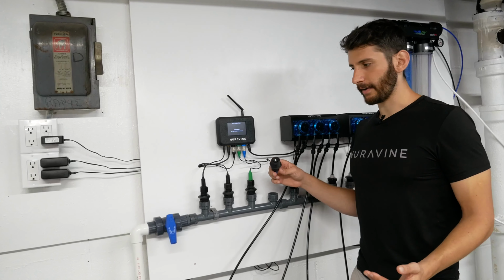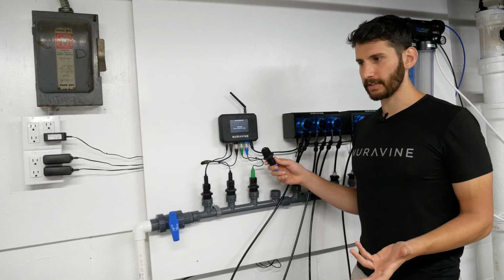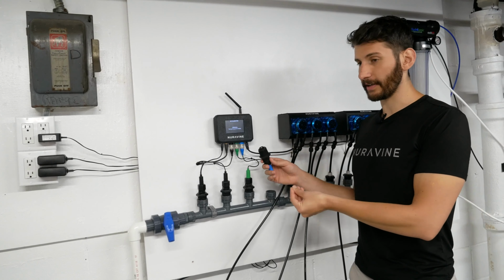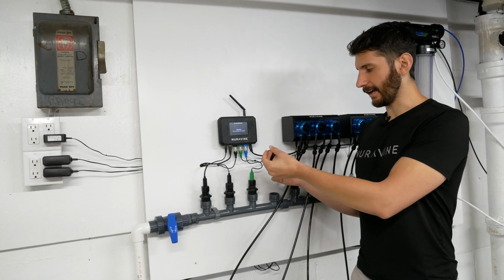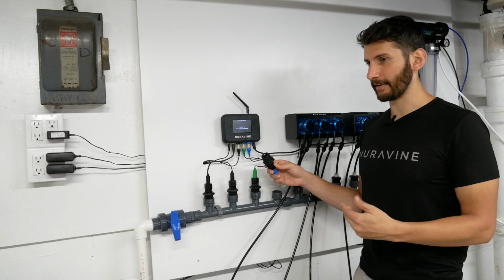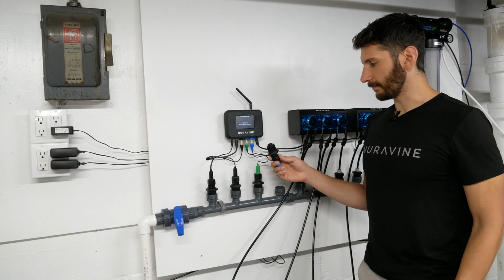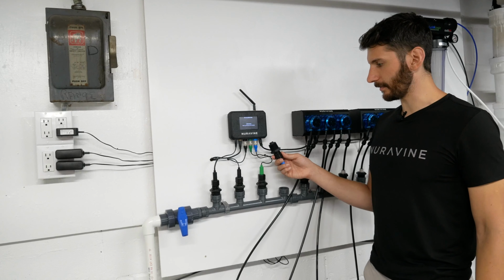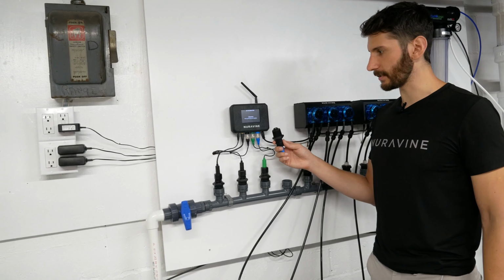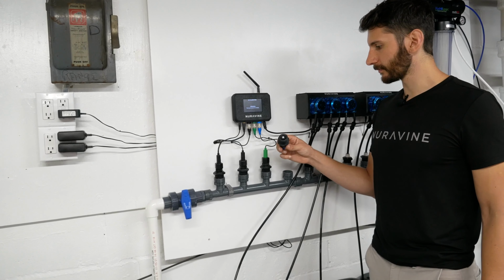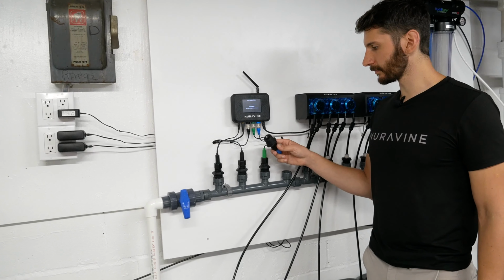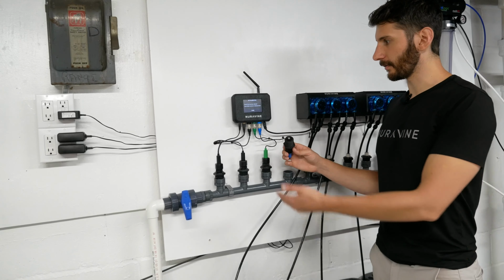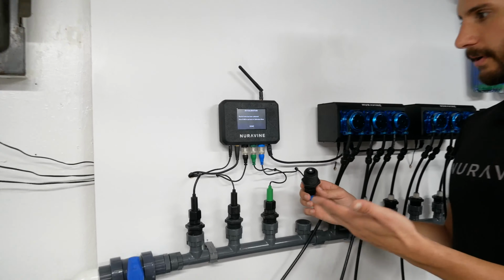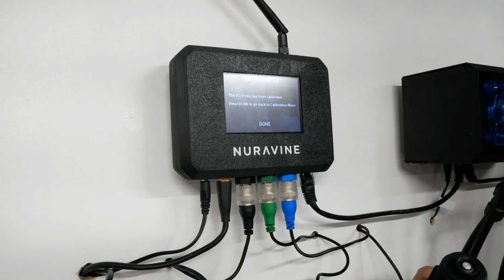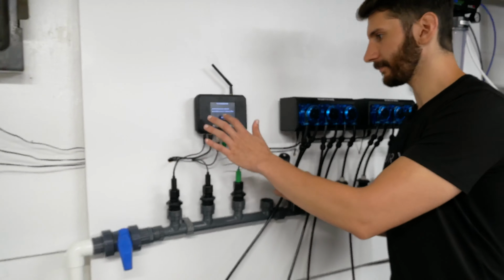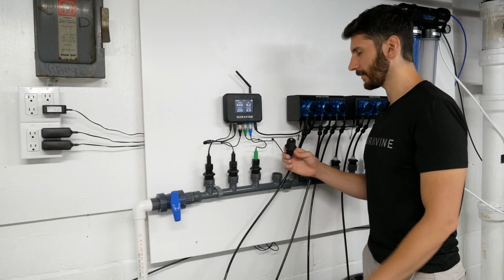Now the reason that I move it around is because this actually consumes oxygen. So theoretically, if you leave it in the very same spot, oxygen could be taken away from that spot, and then eventually the oxygen levels will go down. It's very little, so nothing to worry about, but just moving it around is going to ensure you get the most accurate reading. All right, so now it shows that the DO probe has been calibrated, and we're going to go back to the calibration menu. So we're going to click Done, and we're going to click on the home screen.